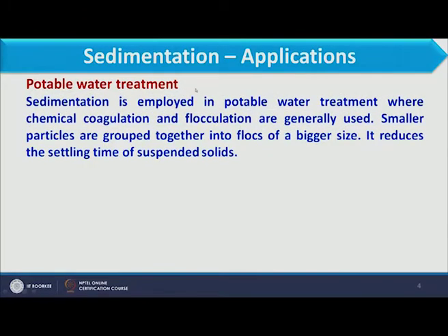Now, we will see its application. The application of sedimentation is again to have clarified liquid and the sludge. It is used in potable water treatment plants, where sedimentation is employed along with chemical coagulation and flocculation, which are generally used. Smaller particles are grouped together into flocs of a bigger size. It reduces the settling time of the suspended solids.